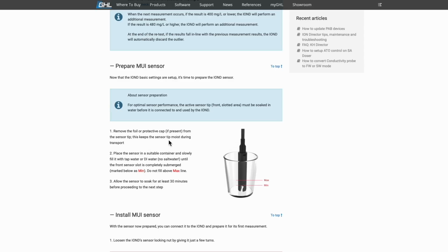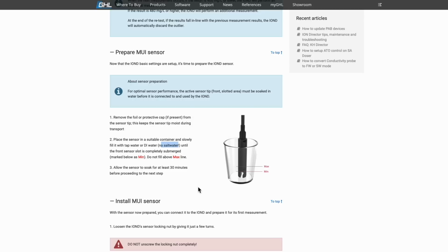Nope, had neither of those from the sensor. Keeps the sensor tip moist during transport. Nope, didn't have that. Place the sensor in a suitable water container and slowly fill it with tap water or DI water. No salt water. So tap water's fine until the front sensor slot is completely submerged, which is this little bit here. Allow the sensor to soak for at least 30 minutes before proceeding to the next step.